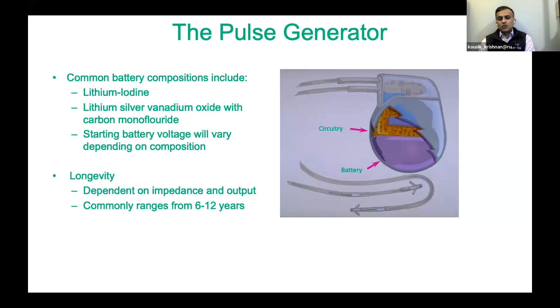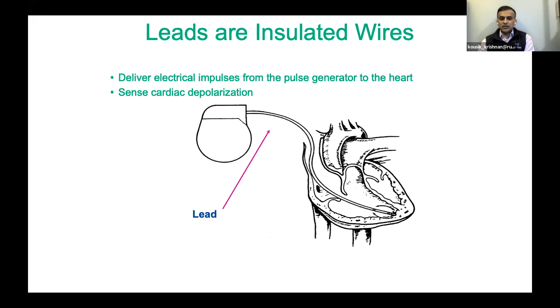The leads themselves, which we know are a weak link, but yet have been the link that we have between the pulse generator and the myocardium for many decades. These are insulated wires that transmit signals back and forth. They send signals in the situation where you need to pace the myocardium. They also receive signals back from the myocardium to the pulse generator so that the device knows when a patient needs pacing and when they're having their own intrinsic cardiac depolarization, which would then trigger the device to inhibit pacing.